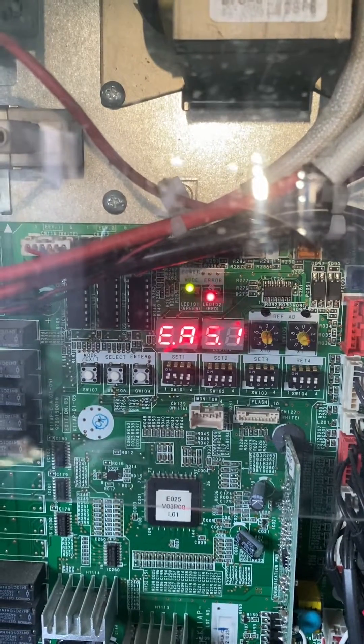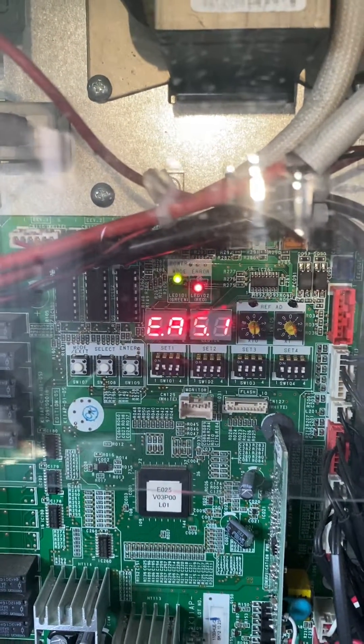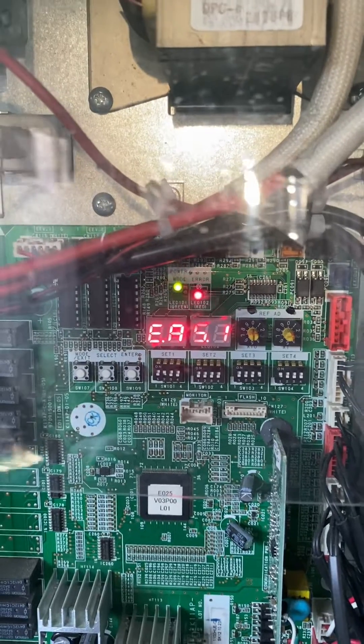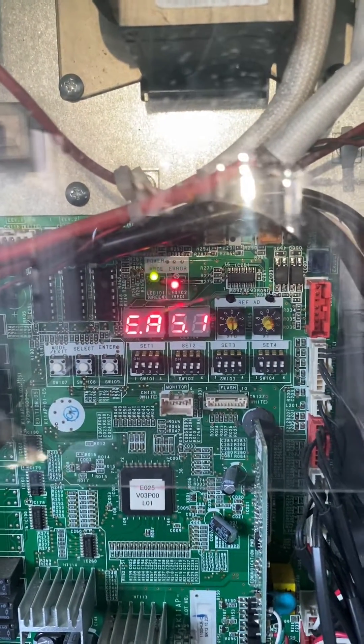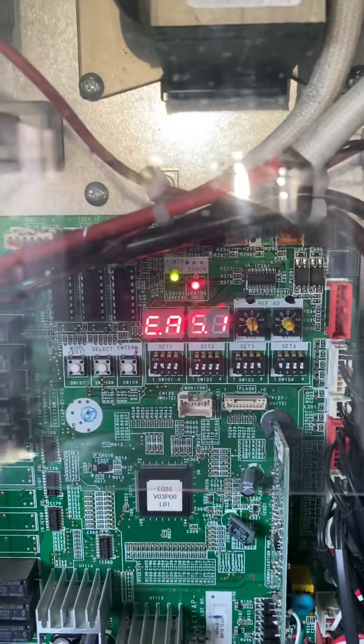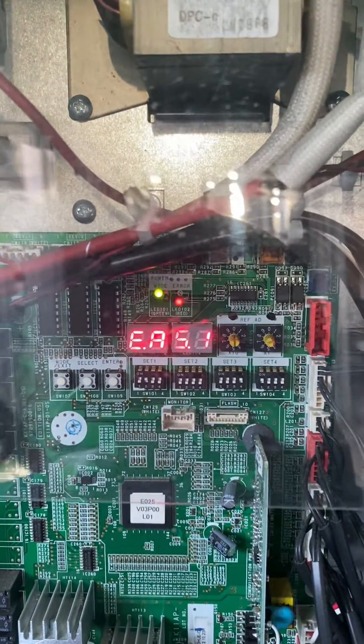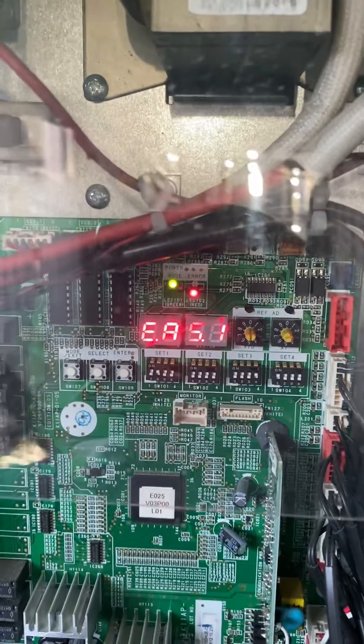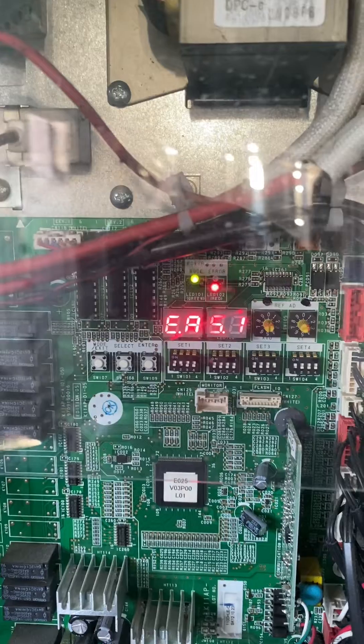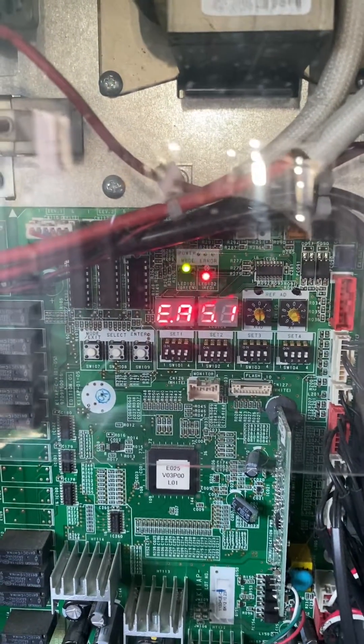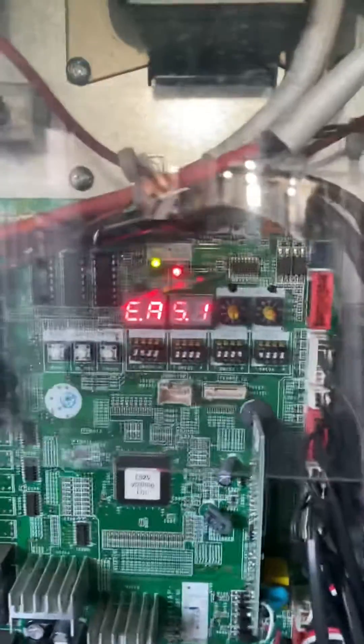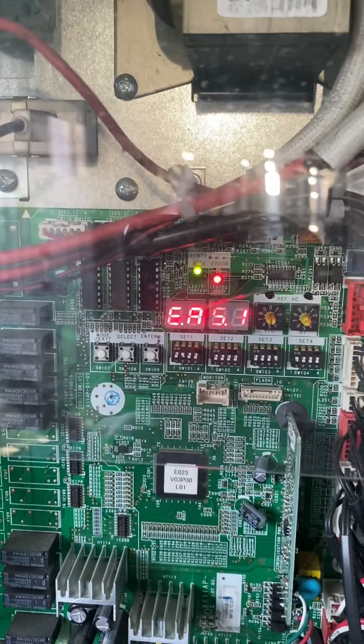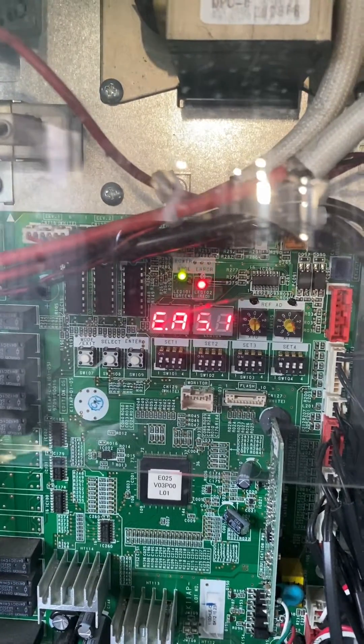Which is an indication of either the four-way valve not open, the EEV is stuck, or mainly the low pressure sensor is either faulty or the system is very short on refrigerant. In this case, I checked and the unit is short on refrigerant and has a leak.